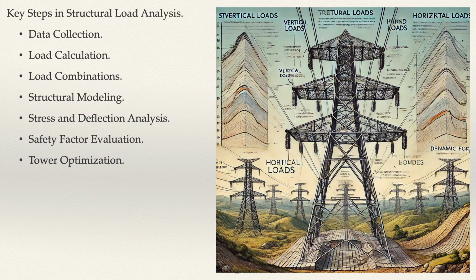3. Load combinations. To account for extreme conditions, different combinations of loads are analyzed, such as: A. Normal conditions: dead load plus wind load under normal operating conditions. B. Extreme conditions: dead load plus maximum wind load plus conductor tension. C. Special conditions: ice load plus wind load during icing events.